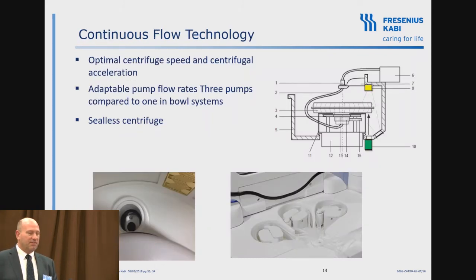With our device, we have really low centrifugal forces. Even though it's a larger diameter, we flow at about 2,400 at the most, but our centrifugal forces on the blood are about a third of competing devices. We have 3 pumps doing the job of 1 pump. This gives the illusion that we're really slow. I don't know how many people always say this is a great pediatric pump or device, but we're not going to use it, we're afraid it's not going to keep up.